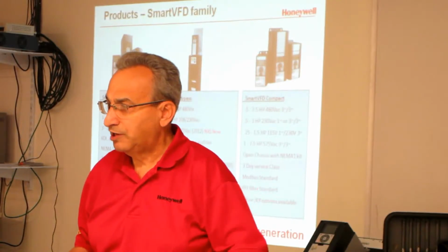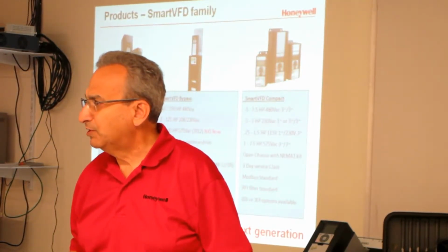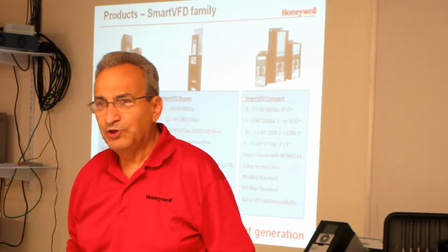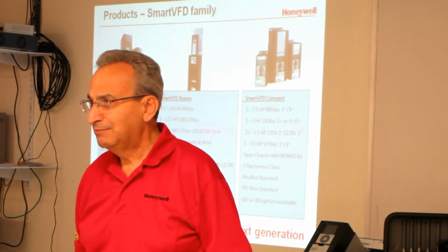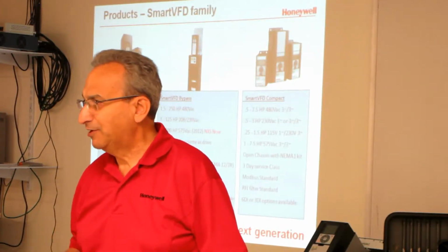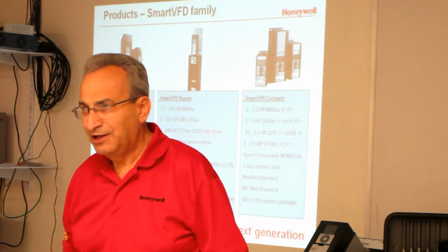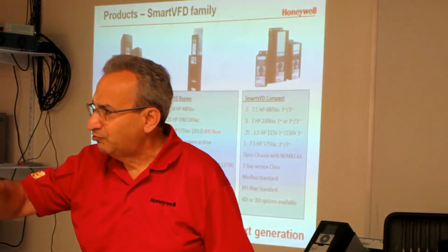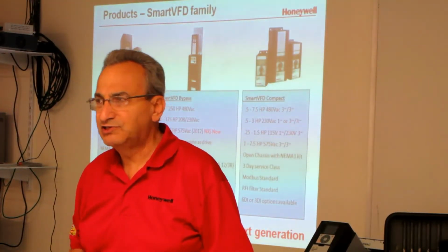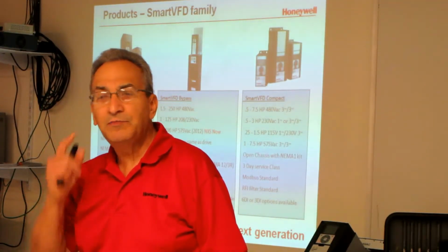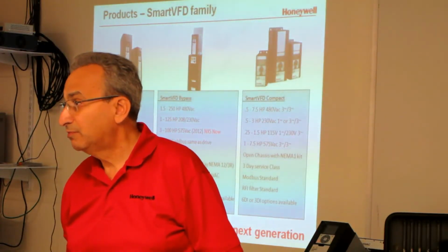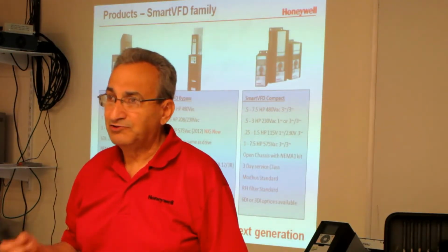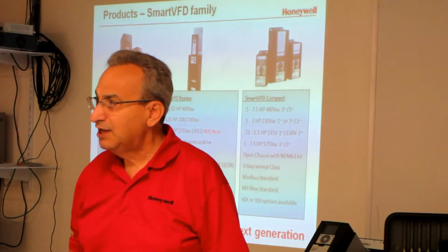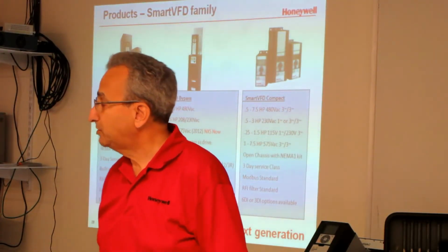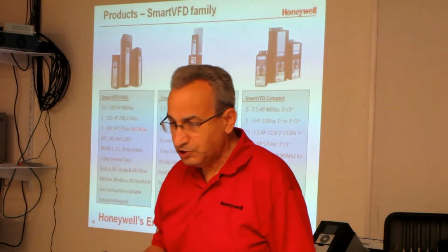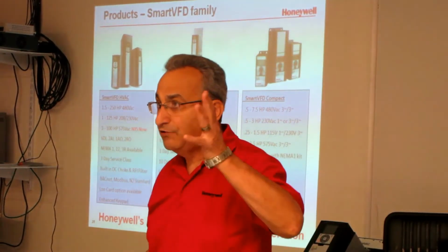So it's actually broadcasting. I don't know if you guys are old enough to remember, but in the old days, this is an AM station. That's where all talk radio is now, but AM station. And we tune it to like 1200, and all of a sudden you pick up the station that's on 600. Well, how am I doing that? Well, you're picking up a harmonic of that station on your radio. Radios are better, transmissions are better at filtering those things out today, but you still get harmonics. Well, you get the same thing on a drive. You got this frequency going out, and the harmonics come out, the high frequency and low frequency.